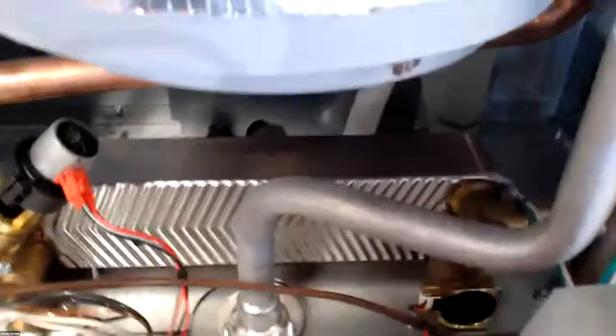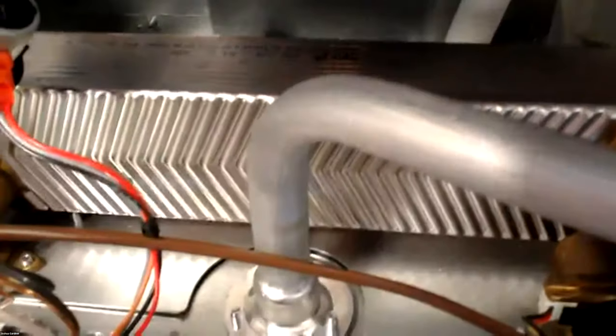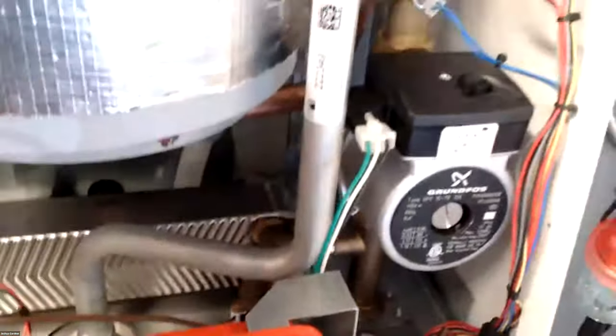Then going into our flat plate heat exchanger, which is located in the back here. We use a pretty generous flat plate heat exchanger for surface area to gain our domestic outputs. One thing to note, and you could kind of say this is a sales pitch, but really it's an efficiency thing, is that we're running about 160 degree water. So we're pretty close to condensing, and we're running in the 90% efficiency on our domestic water production.